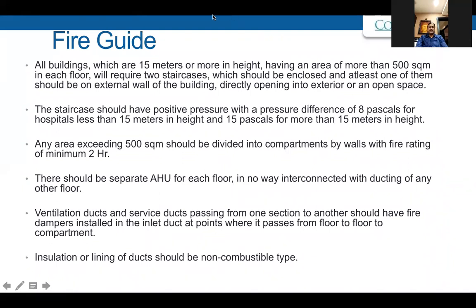So for positive pressure, you have to have the blowers which are created in this area at the time of construction, or it can be retrofitted also. And you can see also that the 2-hour fire rating is now compulsory. And all the air handling units must have separate connections. They cannot be connected with each other. Also, the ventilation ducts which are there must have a fire damper. That means as soon as the smoke enters into that, it gets closed automatically. And it should be of non-combustible material. Next, sir.